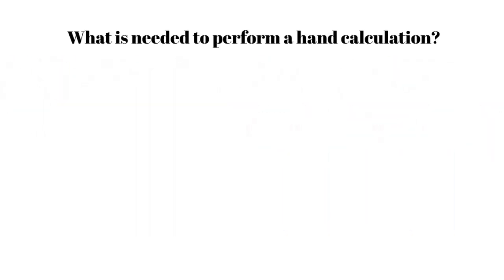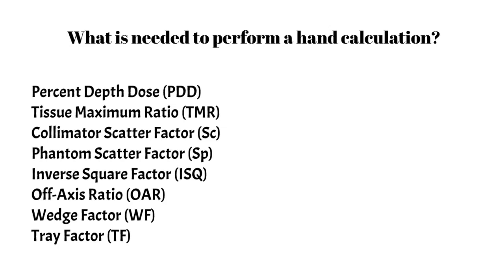But what kinds of data do we actually need to perform one of these calculations? I mentioned a few already, but often many factors go into the calculation, such as the percent depth dose, tissue maximum ratio, the collimator and phantom scatter factors. You might need an inverse square factor or an off-axis ratio, a wedge factor, a tray factor. These are the main components that go into a hand calculation, and I will cover these in detail in subsequent videos.